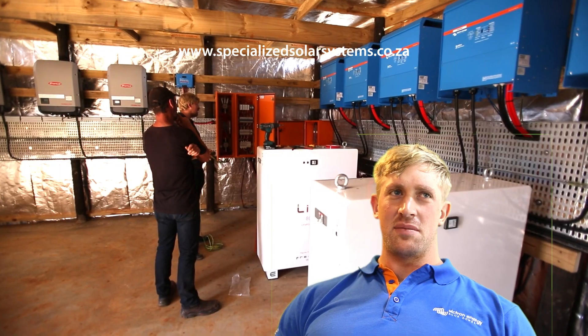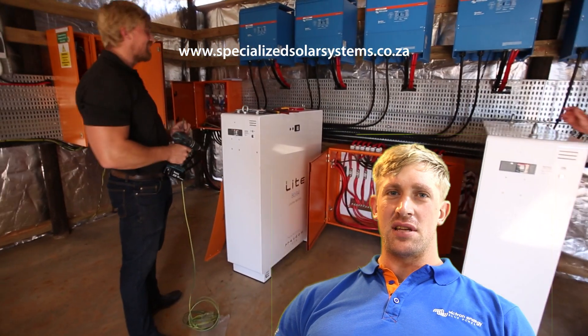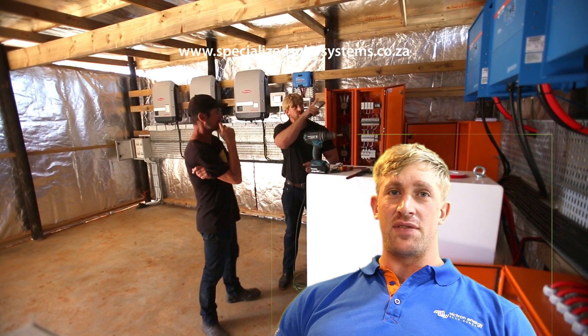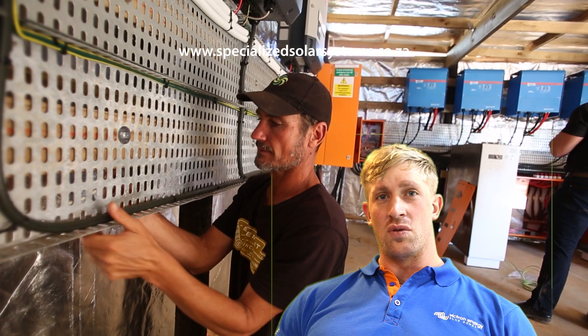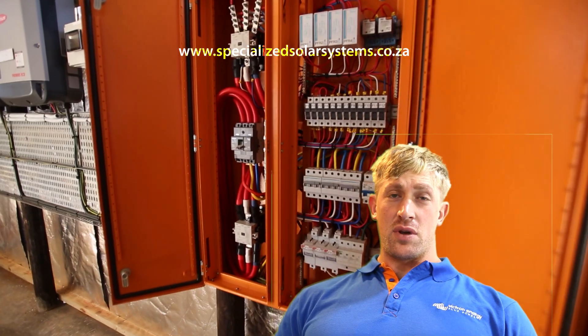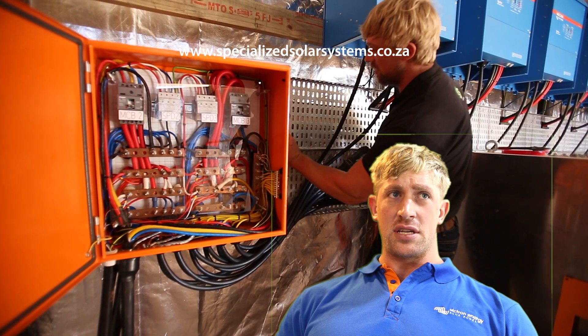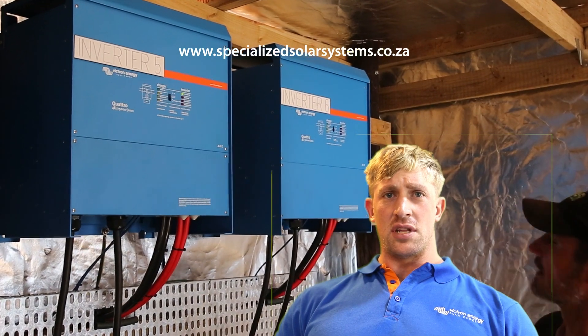Eskom has certain standards we have to adhere to, so we follow their procedures and protocols. We had to install contactors and grid monitoring relays to establish a safe disconnect from the grid, making it safe for them to work on the lines during an outage or maintenance. We also had to establish a network connection on both the Fronius and Victron sides to ensure correct communication, otherwise the frequency shifting wouldn't be established correctly.